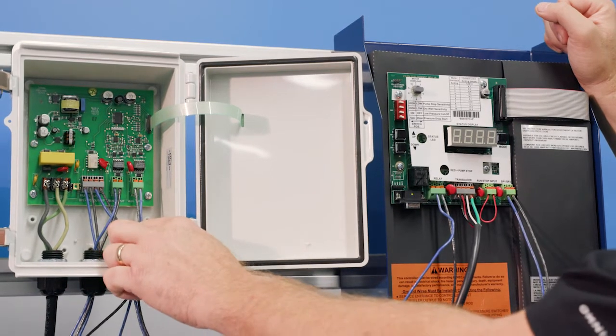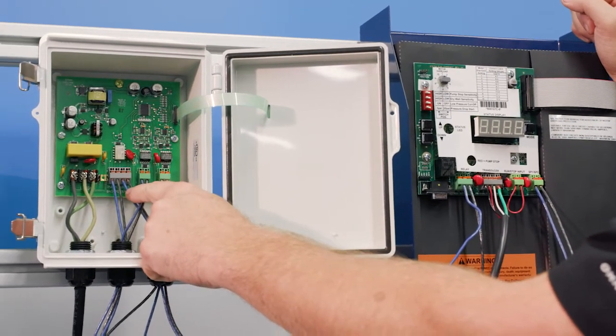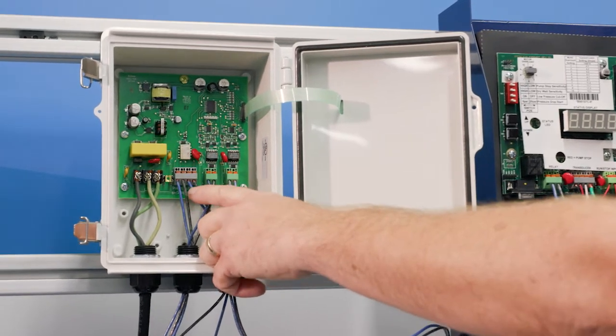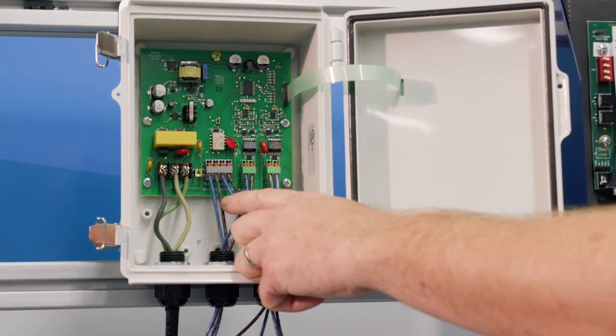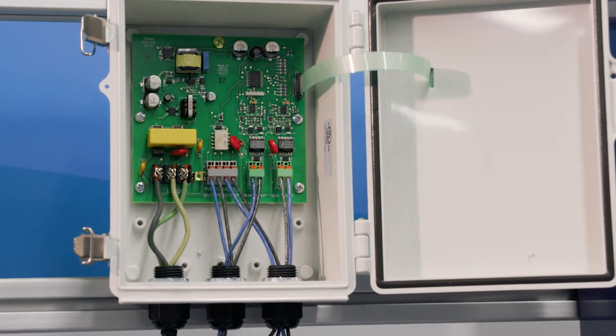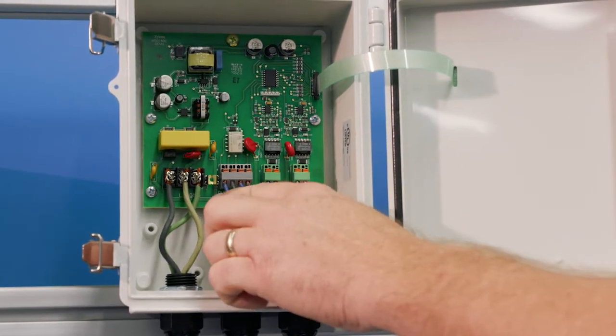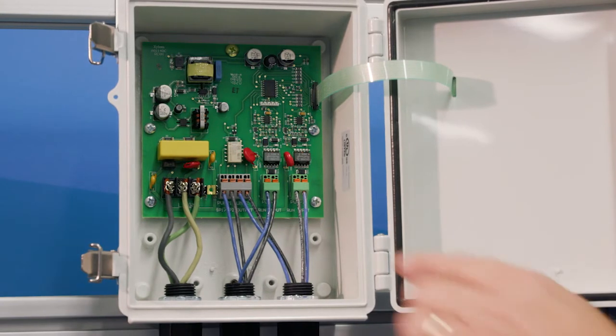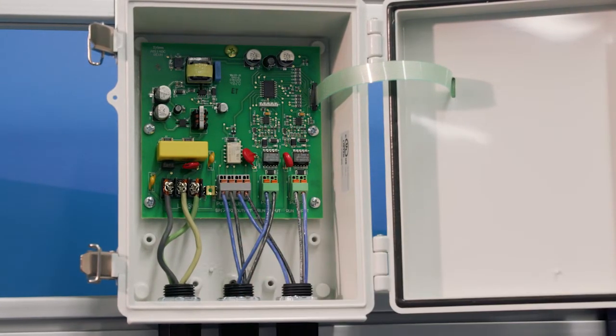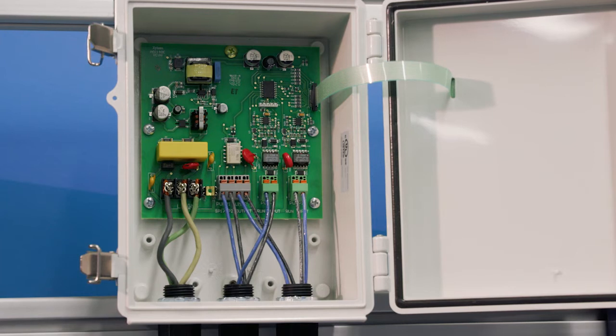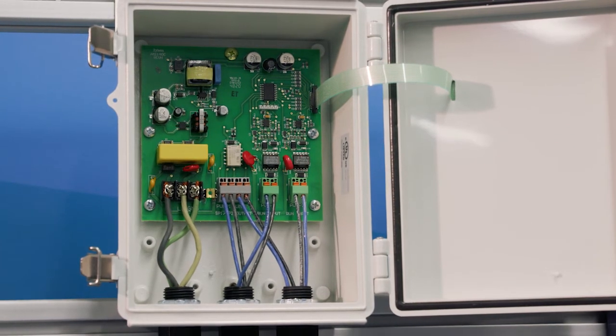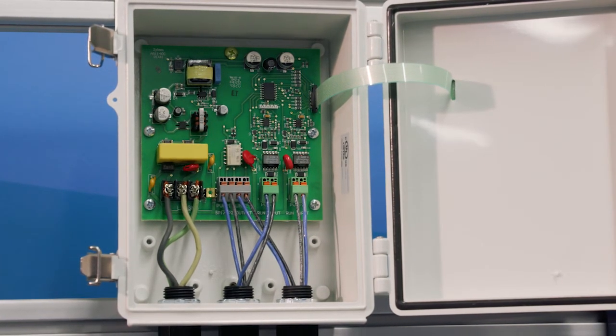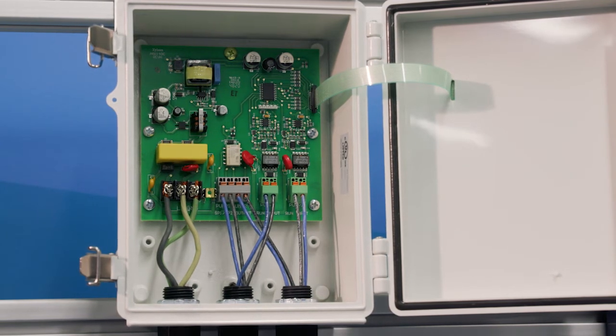The nice thing about this is all of this wiring here does not change, regardless of lead lag alternation runtime or elapsed time. So this doesn't change. If you want to wire this up with duty standby, that basically means that you do not want both pumps running at the same time. If you want to wire it based on duty standby, then you have to look at the installation manual because that is not in the quick start guide.